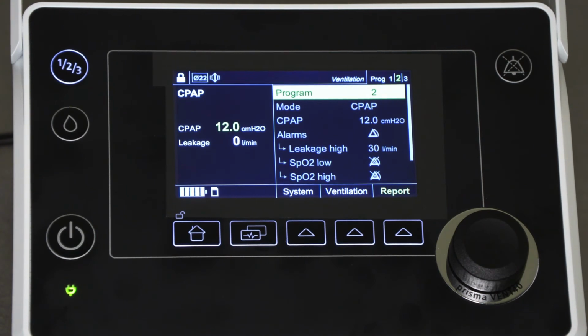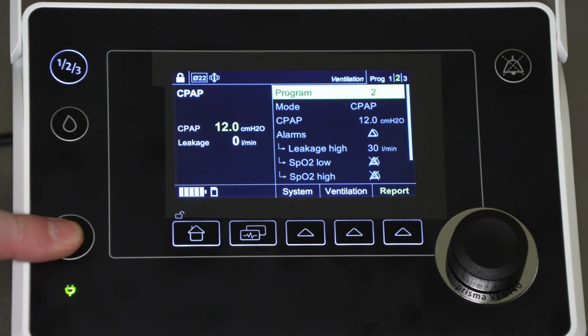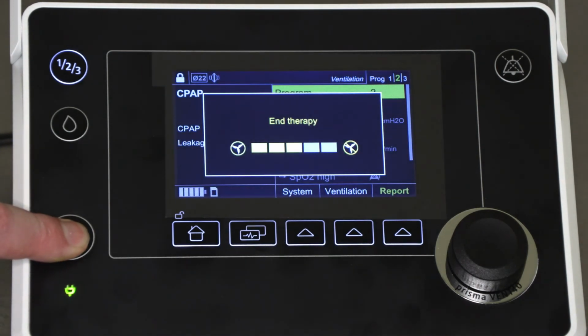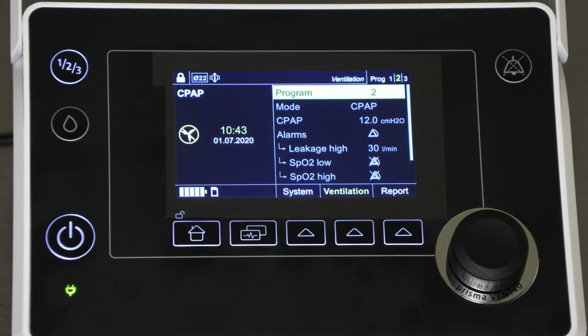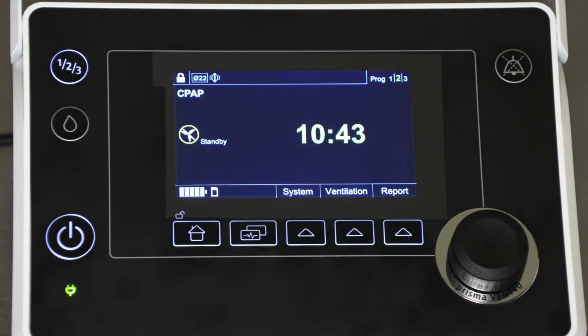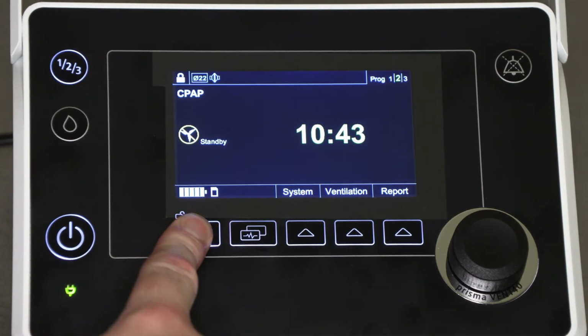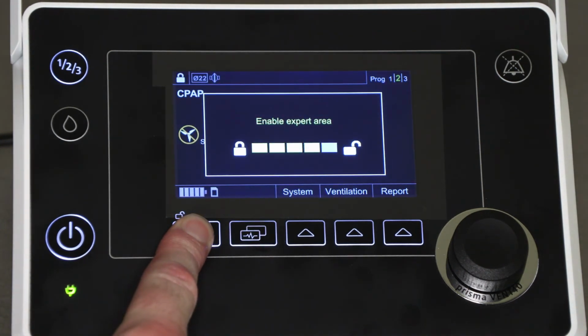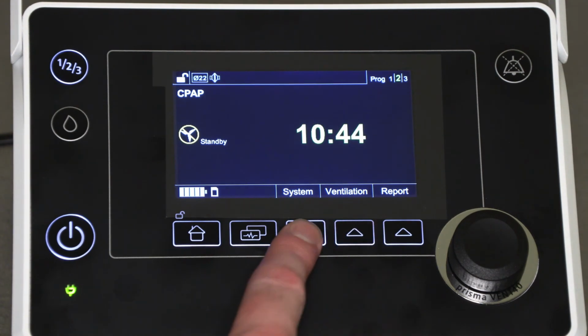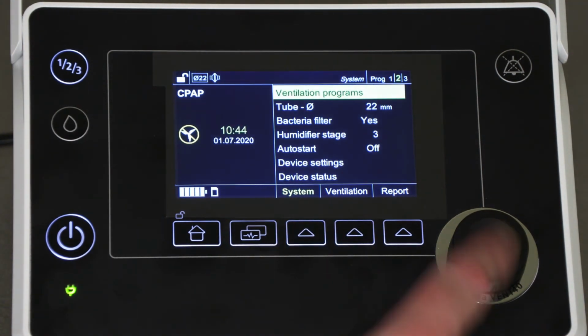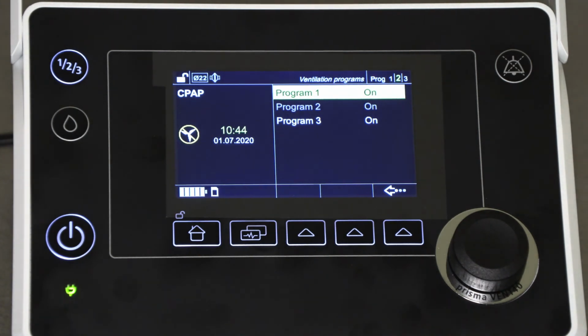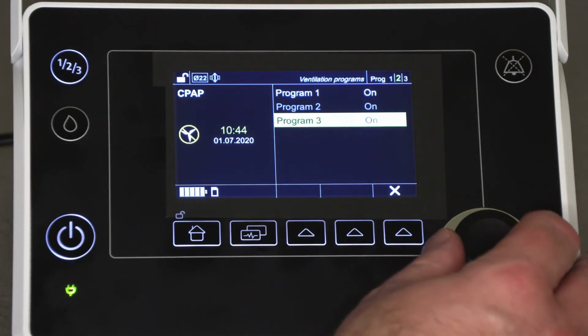It's that simple. Up to 3 ventilation programs with different therapy modes and therapy settings can be set on prismaVENT 40 and made available to your patient. However, if you're only ever using the device in a situation where you only want one therapy mode to be available to the user, press and hold the Home button to unlock the clinical menu. Enter the System menu, select Ventilation Programs, and ensure that only one ventilation program is set to On.